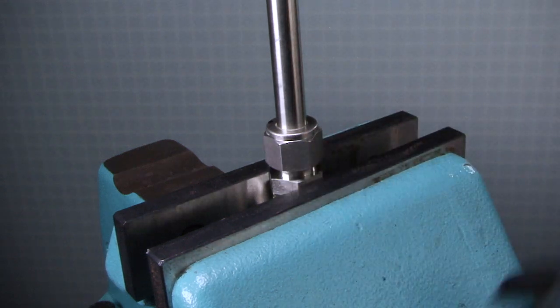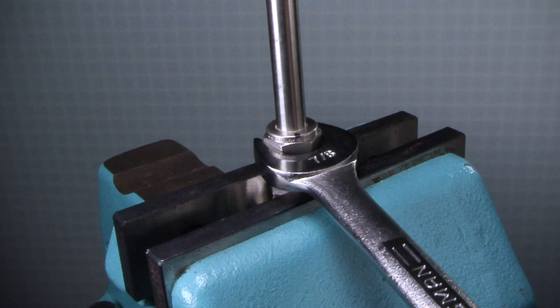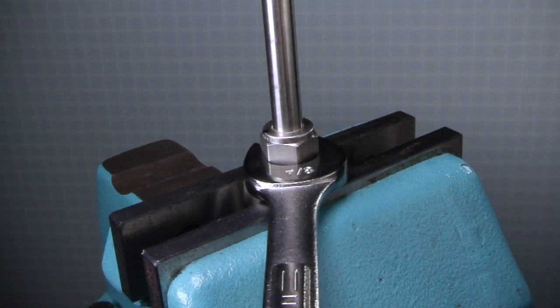Finally, while holding the fitting body steady, tighten the nut one and one-quarter turns to the nine o'clock position.